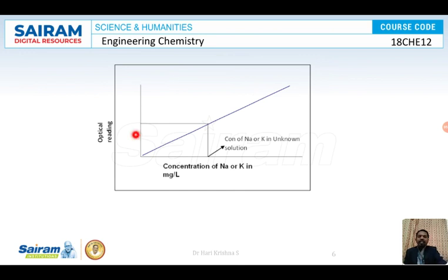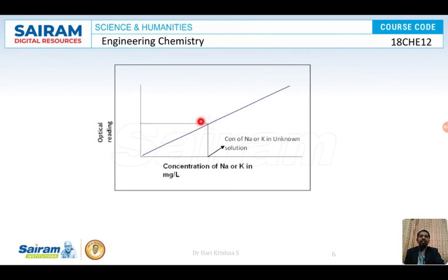The optical readings from the flame photometer are plotted against the concentration of sodium or potassium. For 2, 4, 5, 6, and 8 PPM you have individual readings. For the unknown solution, you have the optical reading but not the concentration. Once you plot the graph, you mark the unknown reading on the intensity axis, draw a dotted line until it touches the curve, then draw a perpendicular line to the concentration axis. That value is the concentration of sodium, potassium, lithium, or calcium in the unknown solution. Thank you.